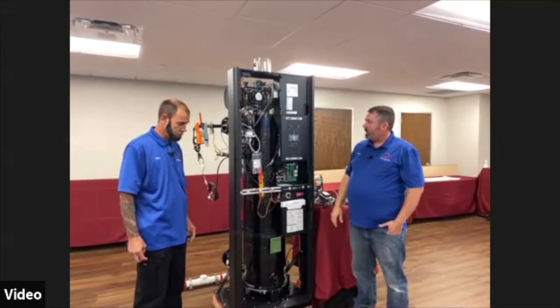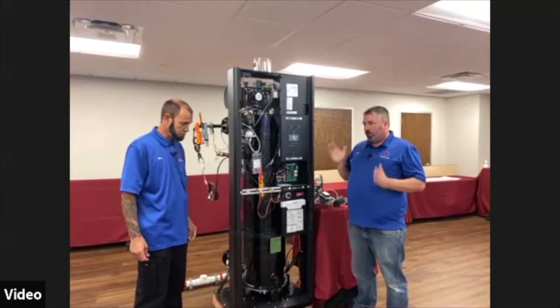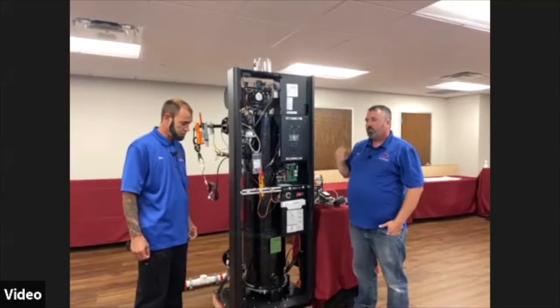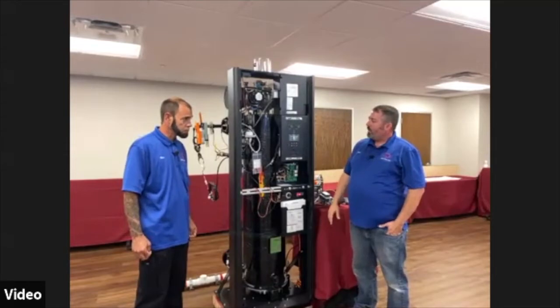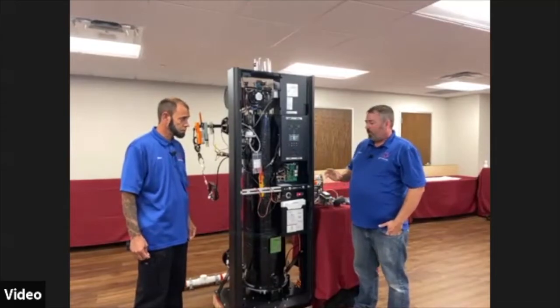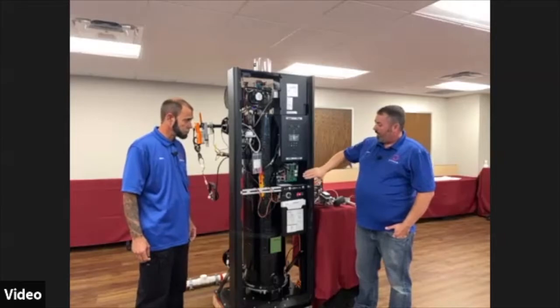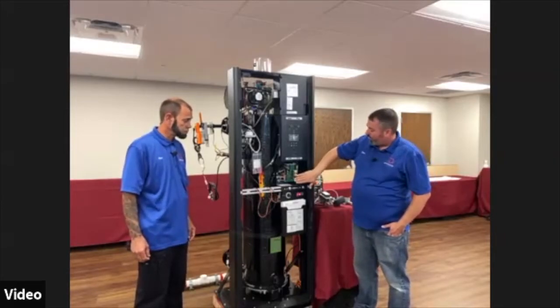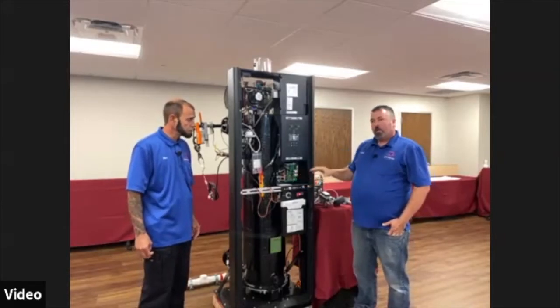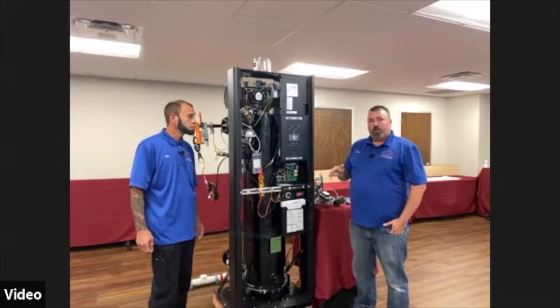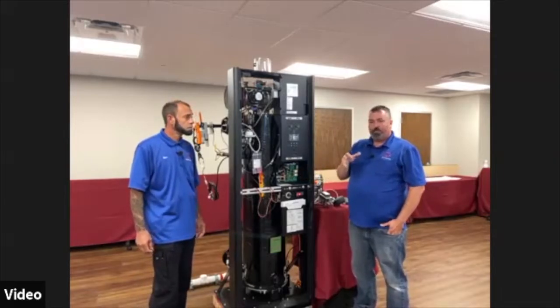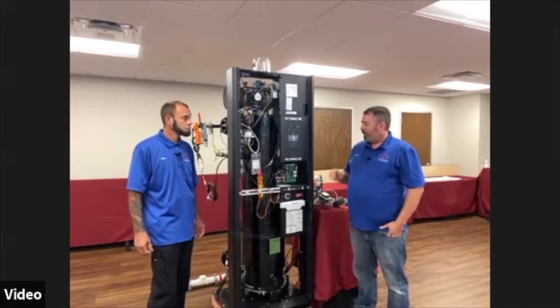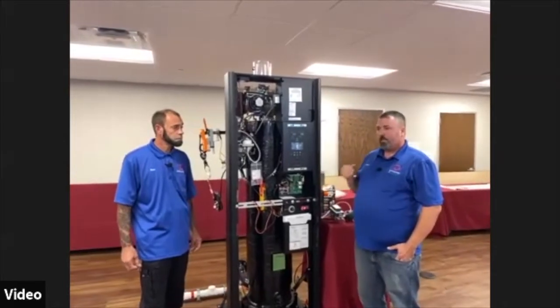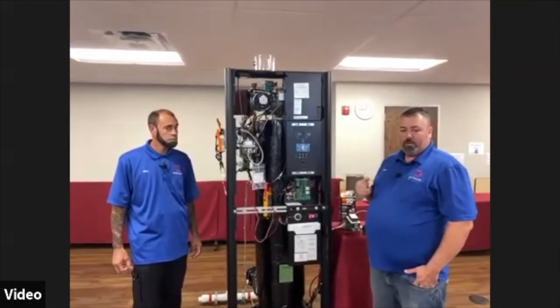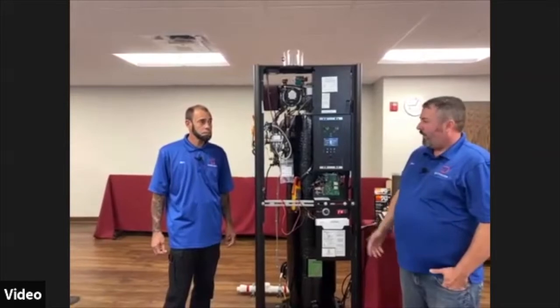It'll adjust it. It'll only go so far until it needs maintenance, and then it'll tell you you have to clean your filter or whatever. The second thing that the Platinums have is what they call onAER technology through the I/O board. There would be another circuit board. What that will do is tie directly into AERCO's factory, right to their headquarters, and they can monitor your boiler plant and let you know if your boilers need maintenance, if it sees an issue. They do a lot of proactive and preventative maintenance through that.